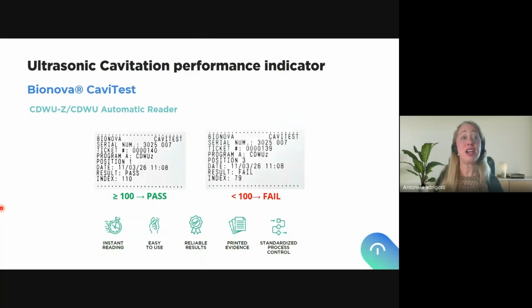Okay? As you can see, the automatic reader will automatically print the ticket with the information you can see on the screen. Two examples, a pass and a failure. You will have the batch and serial number of the machine, the ticket number for traceability between the printed ticket and the digitalization, the program being used, the position being used, the date and time, the result, whether it's a pass or a failure, and the index. So you can see we have an instant reading, it's very easy to use, reliable results, printed evidence, and standardized process control, thus solving the previous challenges of relying just on visual interpretation.